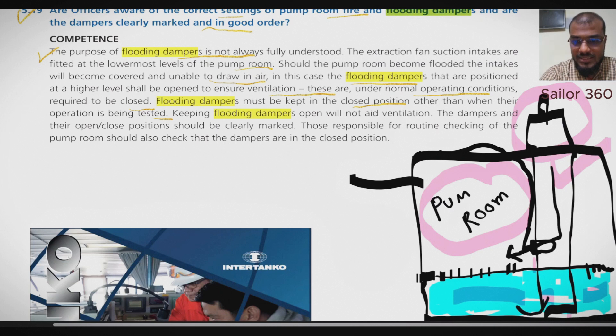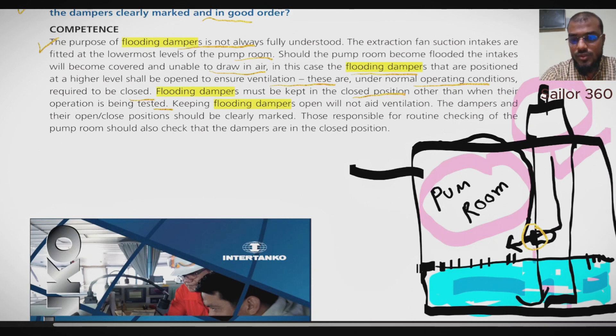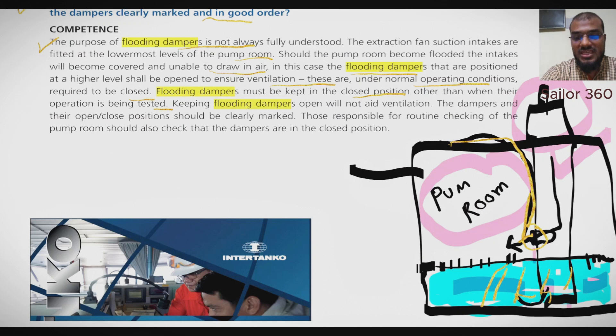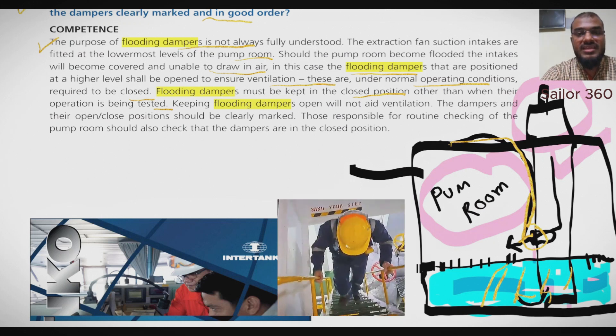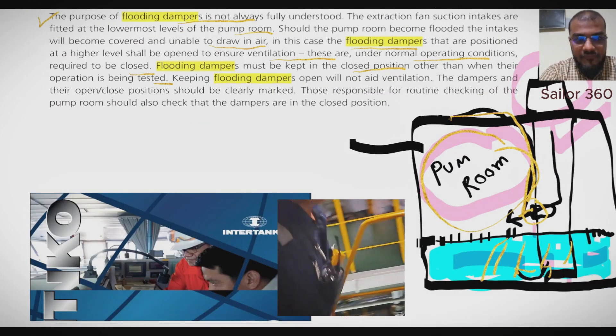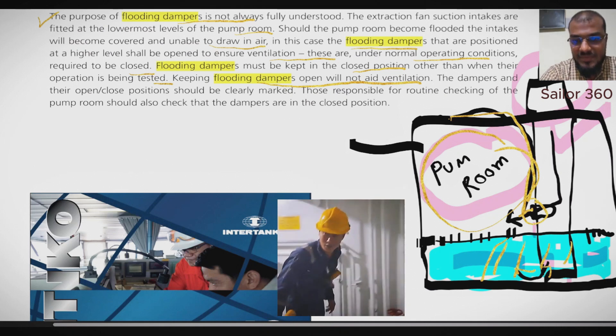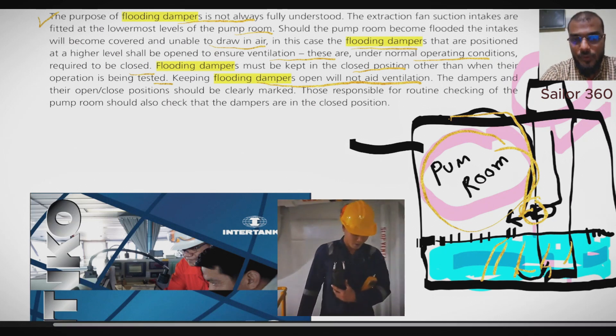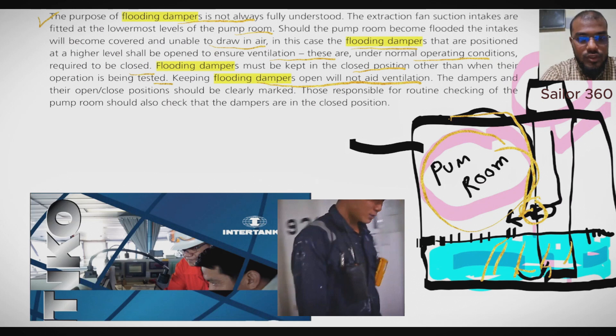We understand from the above reading that the flooding damper should be kept closed during the normal condition of the pump room so that ventilation takes place properly from the down part. But in case of flooding, we should keep this flap open using the remote control system so that ventilation can still continue. Keeping flooding dampers open will not aid ventilation — meaning if we keep the flap open during normal conditions, the ventilation will not be proper.